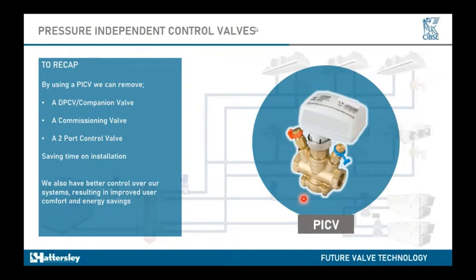So just to recap, by using the PICV, we can remove the DPCV, the companion valve, commissioning sets, two-port control valves, etc. This does save time. As I've mentioned before with the valve authority, because obviously your valve authority with PICV is 1, and because it's a self-regulating valve, we can cut down commissioning times as well, because each valve can be basically set and then forgotten. It just needs the actuator put on there and energized for it to then start modulating. But effectively, as soon as you've set it, and if you've got enough pump pressure throughout your system, these valves will be able to perform to what your designs have been intended for them.